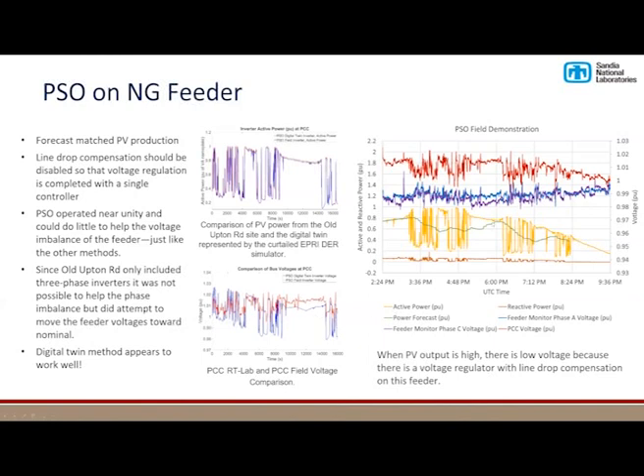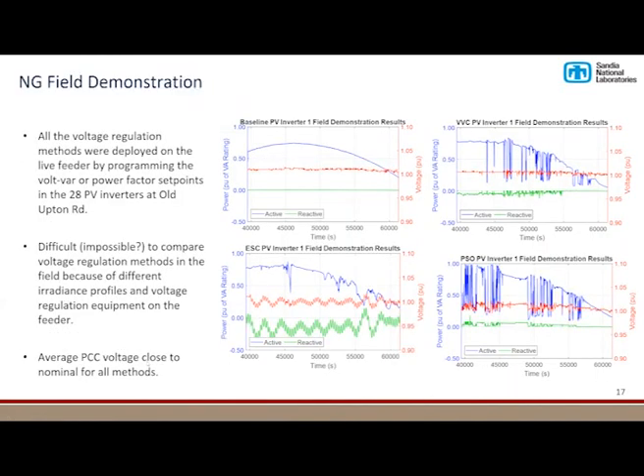For the optimization, as we saw before, there's not a whole lot that it can do. The average voltages are shown here for the feeder monitor in the blue and purple increasing, and then the point of common coupling in red. The active power is the yellow line, and the green line is our forecast, a persistence forecast, longer term, more of an energy forecast than an actual power forecast. The reactive power contribution is relatively small, shown here in orange. So it seems to work reasonably well. I won't say it's perfect, but in order to run this optimization, it was a good technique.